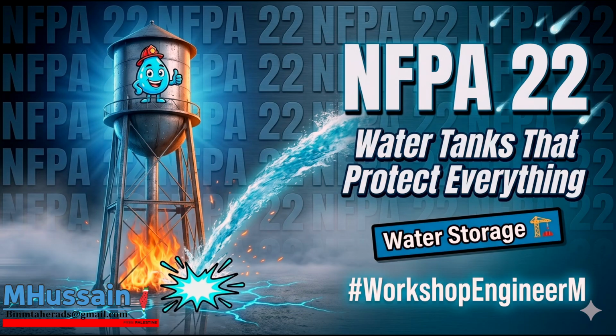It's almost never the pump itself that fails in that situation. No, it fails because of something like a localized invisible velocity gradient in the water supply tank that induces a vortex. Or maybe a single discharge elbow experienced catastrophic thermal stress overnight. Because it froze. Right. As a safety engineer, you know this harsh reality. The water source is your foundational failsafe. If that water supply goes down, the entire meticulously designed system downstream is just an incredibly expensive network of, well, useless metal.